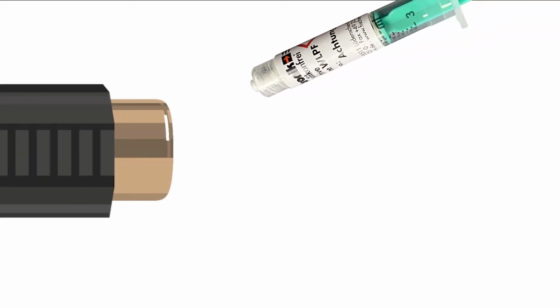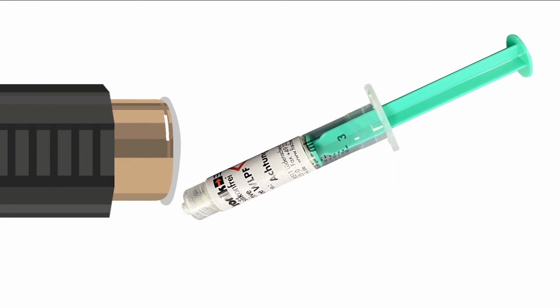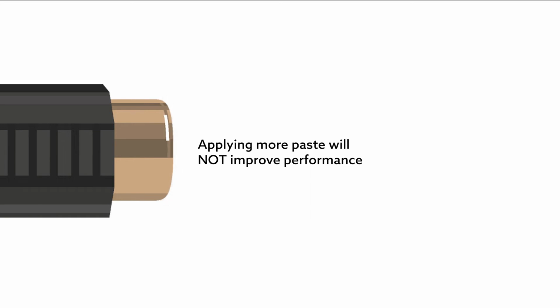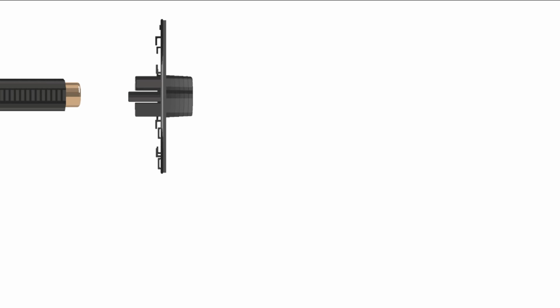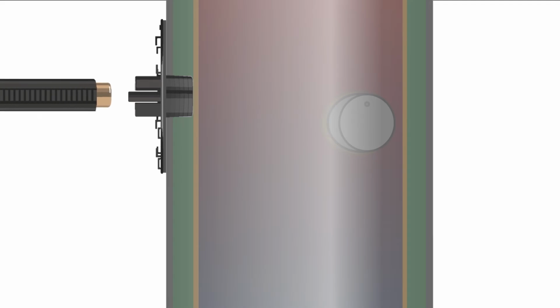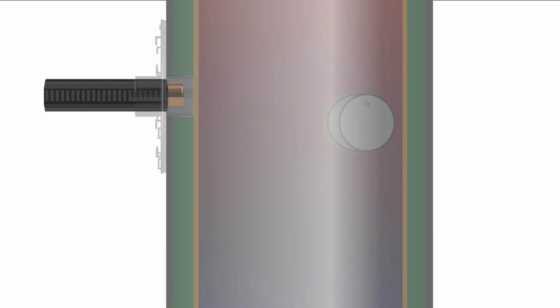The thermal paste in the syringe should be applied to the copper head of the tank probes before they are inserted into the bores. 1 mm across the whole surface is the optimum amount. It is important to have consistent coverage. Applying a greater depth of paste will not improve performance. Insert the probe sensor through the upper mounting flange and push until you feel the copper head meet the tank's surface. Use the ratchet to ensure the spring is compressed. Repeat this process with the lower sensor.